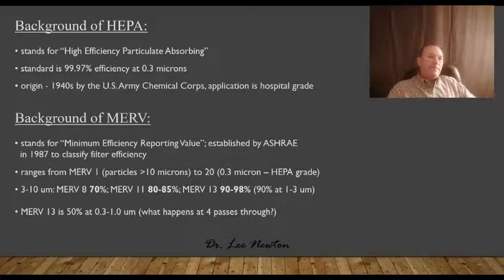So HEPA stands for high efficiency particulate absorbing, and the HEPA standard is 99.97% efficiency at 0.3 microns, developed by the U.S. Army Chemical Corps in the 1940s, and it's essentially a hospital grade application.